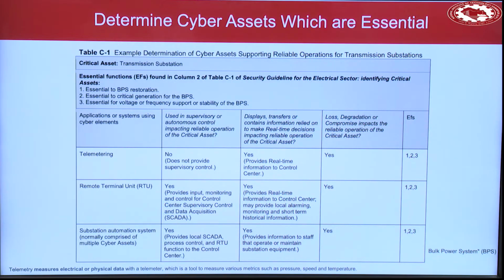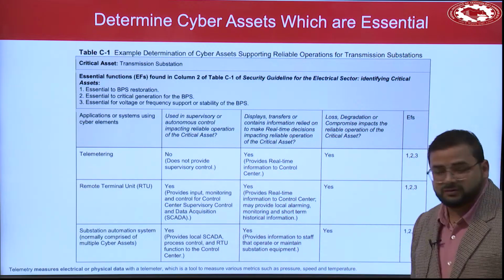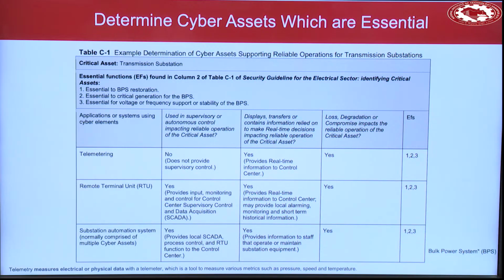RTUs - remote terminal unit. What is the role of RTU? These are the devices deployed at substations. They are sensing, fetching data from all other devices and sending it to the control center. And when I say sending to the control center, they are sending to the SCADA system. SCADA system feeds all the data and runs the algorithms. So RTU is essential for SCADA systems. If there's no RTU, you don't have any data.